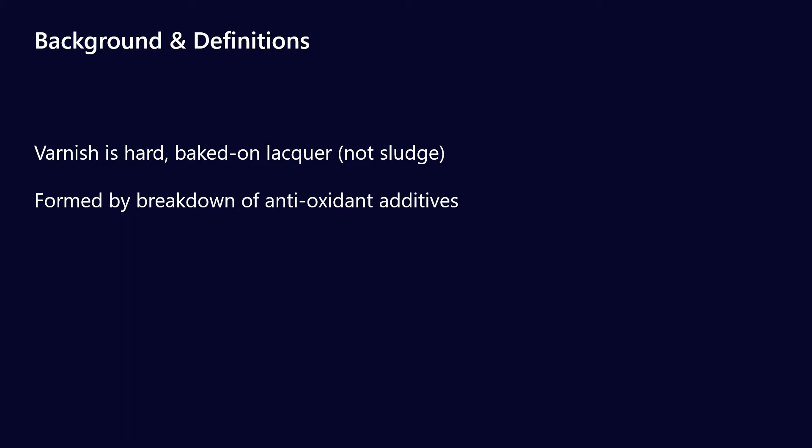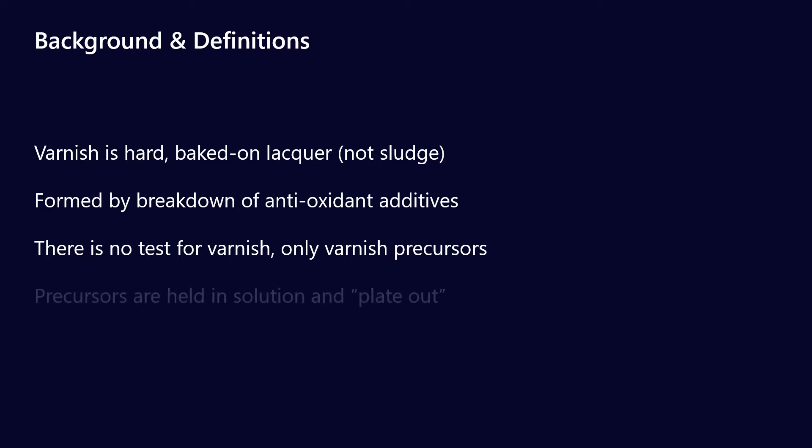The breakdown of the antioxidant package is the predominant material that goes into making varnish. There's also no direct test for varnish itself. We can test for varnish precursors in the oil, look at the oxidation stability of the oil, and look at the amount of aminic and phenolic antioxidant additives remaining. But we can't actually test whether varnish is occurring — really only a physical inspection will tell you whether there is varnish in your system.